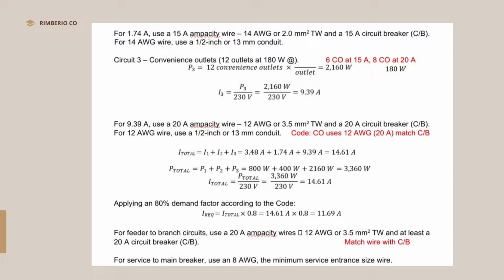So for circuit 3, convenience outlets, 12 outlets at 180 watts. So electric power P sub 3 is equal to 12 convenience outlets times 180 watts per 1 outlet, which is equal to 2160 watts. Next is electric current I sub 3 is equal to P sub 3 all over 230 volts. So equal siya sa 9.39 amperes. So for 9.39 amperes, use a 20A ampacity wire, 12 AWG.